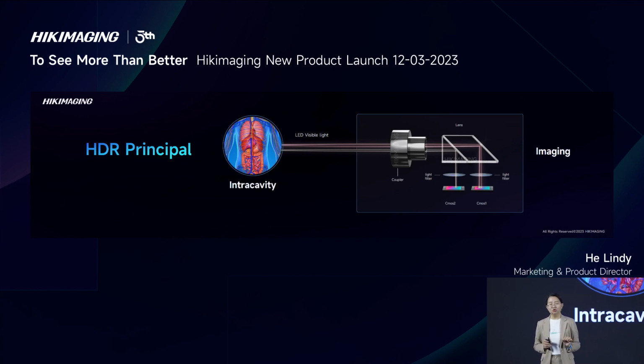So we add an additional CMOS to the camera head. By optical design, we split less light to the near field as its light condition is enough. So the optical design can avoid overexposure. While we split more light to the far field, as it indeed needs more light to prevent it from being too dark. The processor merges the two channels of data from the two sensors and applies an algorithm to realize the fusion of the two CMOS. As a result, we can get a more comfortable and clear vision.